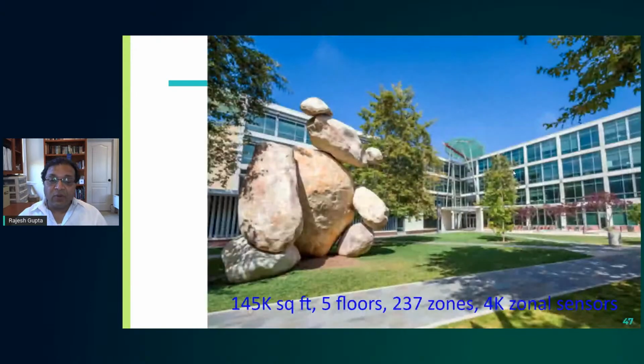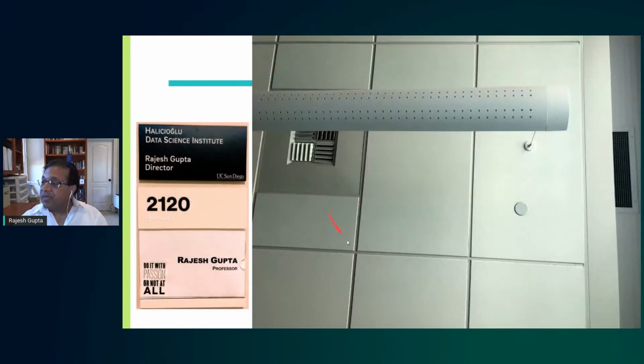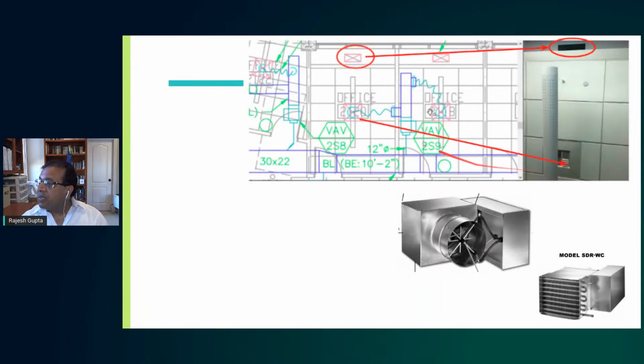So that's it. If you go inside the building, I want to walk you through this a little bit and bring you back to infection control. If you go inside this building, this is my office actually, you will see an air feed. This is where the supply air comes in, and then the return air goes through this common plenum here. This is the actual schematic. You will see that this particular VAV serves 2 rooms. So this is my office.